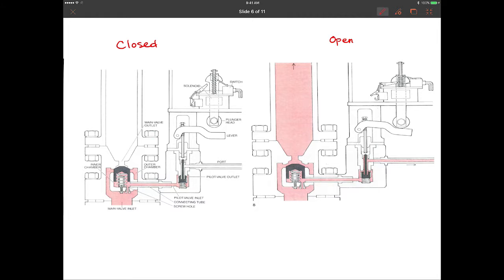And to understand this, we have to look at how the PORV works, or how it's actuated. So this is really the part we're interested in here, and I'll get rid of that so we can continue to make our marks. What you'll see is that the PORV is really controlled by this guy. This is the solenoid. So when that solenoid is activated or receives a signal, it drops the plunger, and this lever is then depressed this way. When the lever goes down, this plunger then goes down and pushes on this plug right here. So this plug is held up by the spring, and when the plunger depresses it down, it creates a pathway. I'll do this in blue so you can see the pathway is opened. Now the inventory can exit into the pressurizer relief tank. So that's how the PORV basically works.